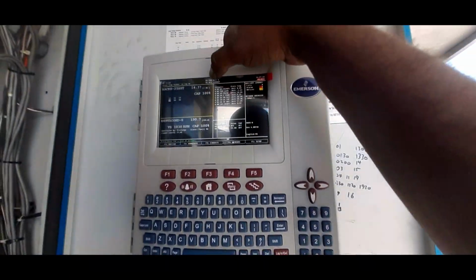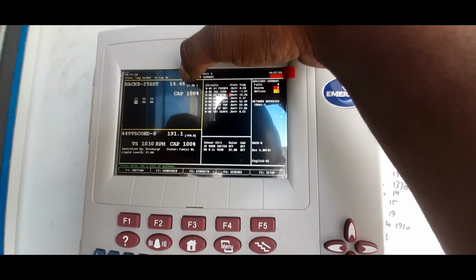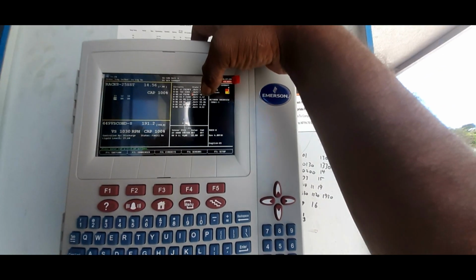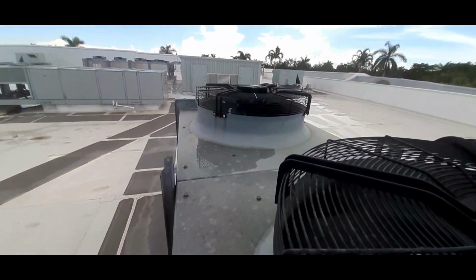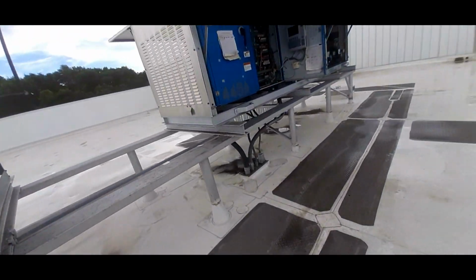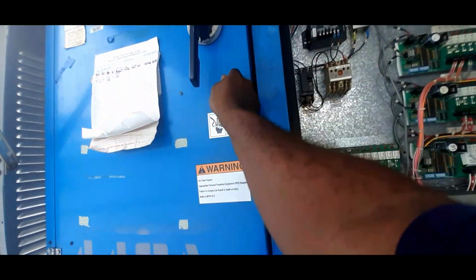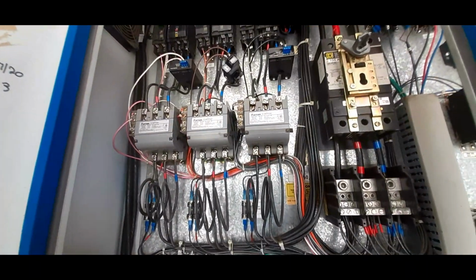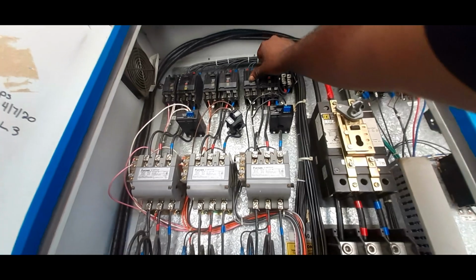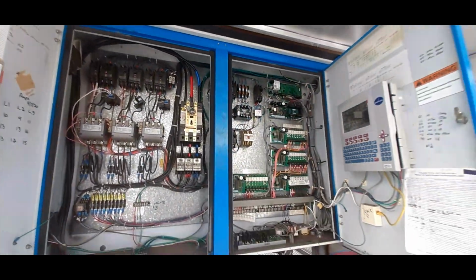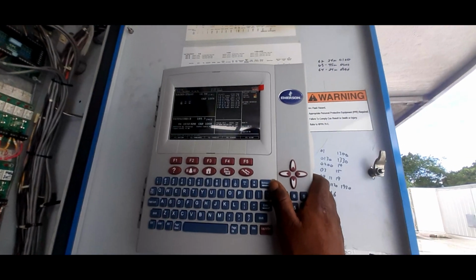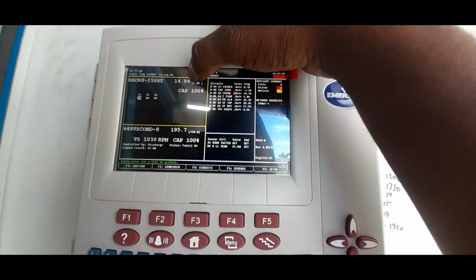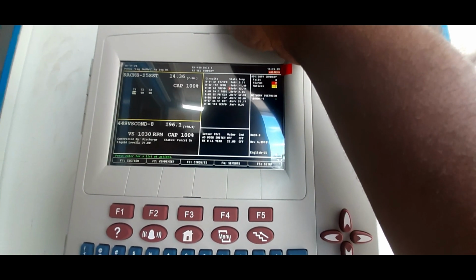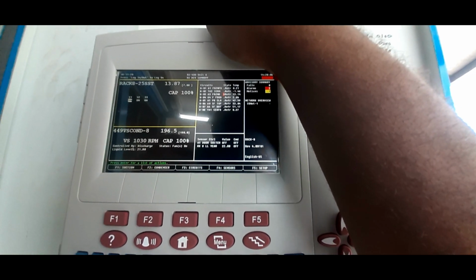So far, we came down to, what is that, 14. Our set point is 7. Now we're down to only one case in alarm. Our condenser fans are running now. Alright, that's a good thing. I wonder if that compressor has cooled down. I don't have my amp probe over here. So we'll hit low voltage and then control voltage. That compressor came on. Look at our set point, our suction pressure. So we dropped down to 13.